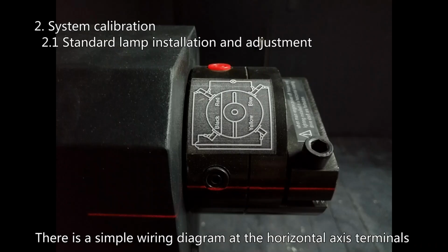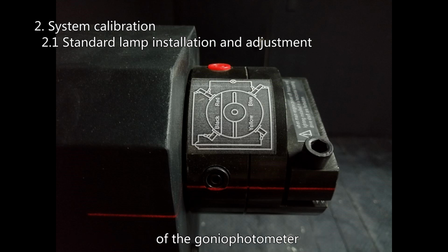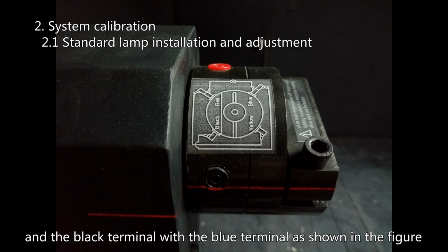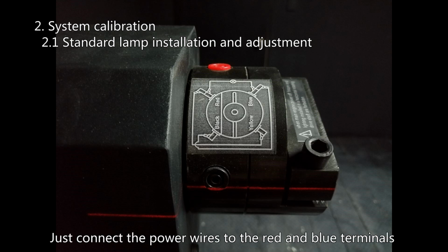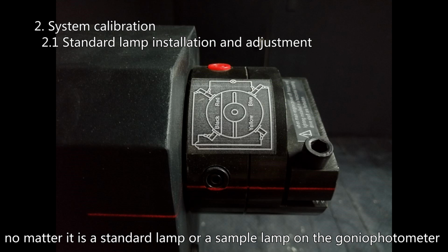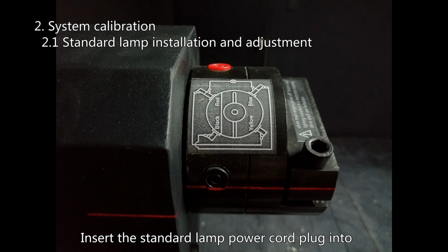There is a simple wiring diagram at the horizontal axis terminals of the goniophotometer. Please use short banana plug wires to short the red terminal with the yellow terminal, and the black terminal with the blue terminal as shown in the figure. Just connect the power wires to the red and blue terminals no matter it is a standard lamp or a sample lamp on the goniophotometer. Insert the standard lamp power cord plug into the red and blue terminals of the C-axis.